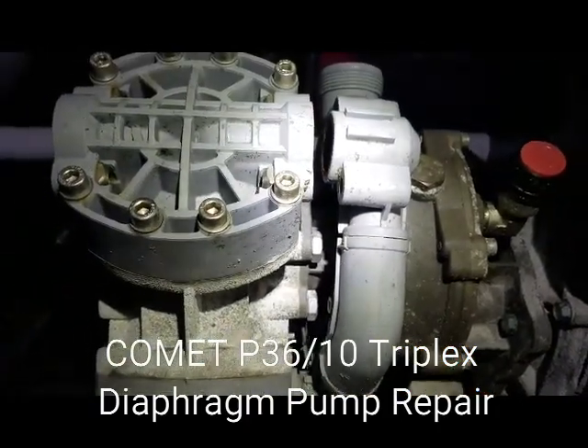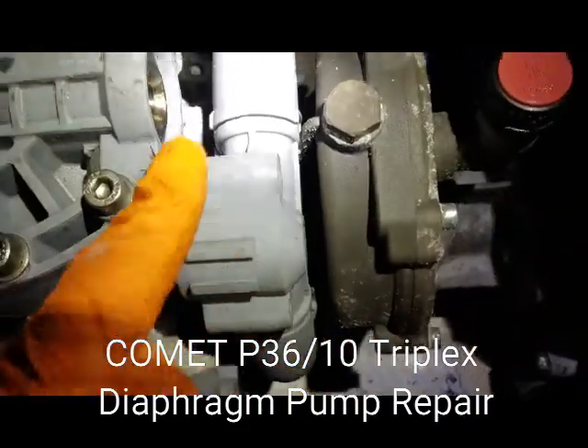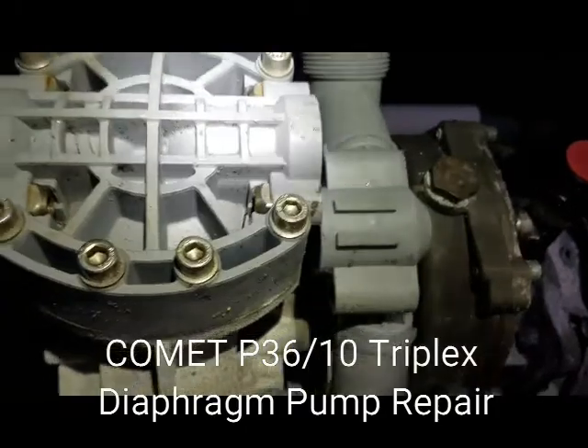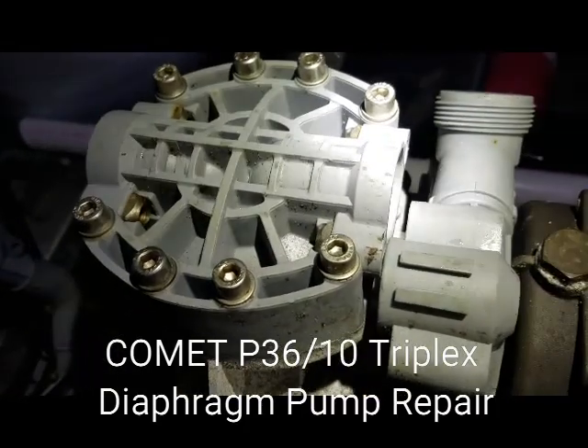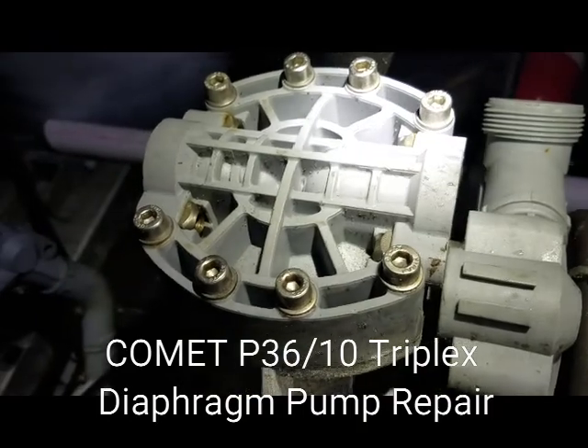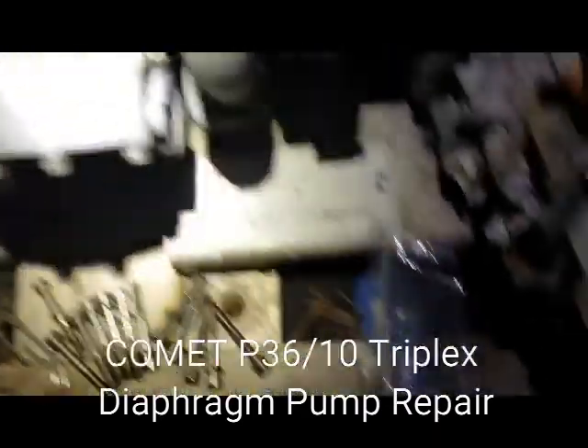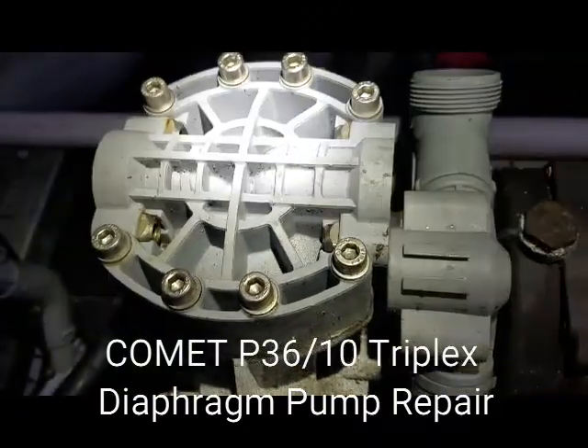All I did was move it just a little bit — that's going to give me nice and easy access. I'll be able to maneuver these pistons out. Inside there you can see it's black — that's partially related to the black particulate that comes out of the bleach. Also there have been times where because of the plumbing we starve the pump for water. The revised plumbing will take care of that. Parts aren't cheap — make sure you are properly taking care of your equipment.